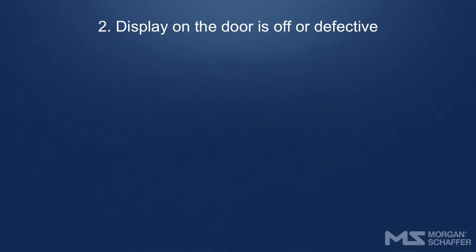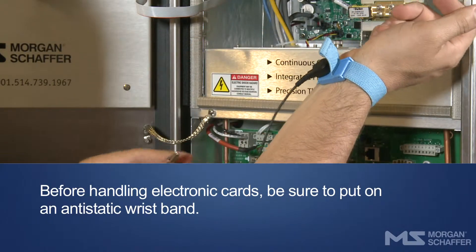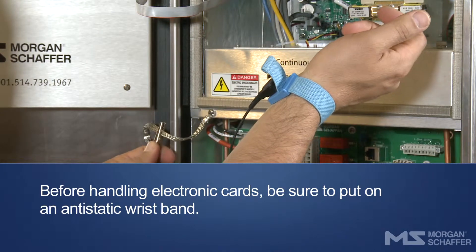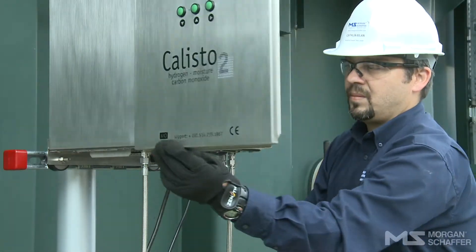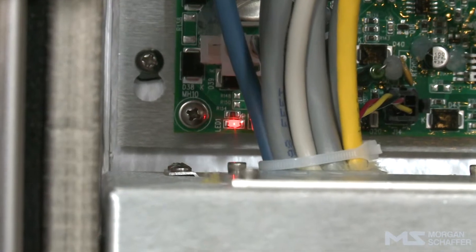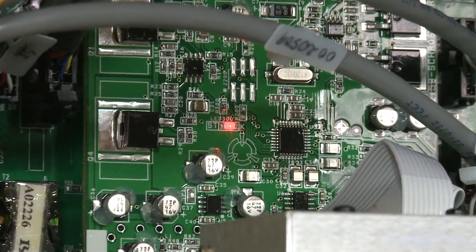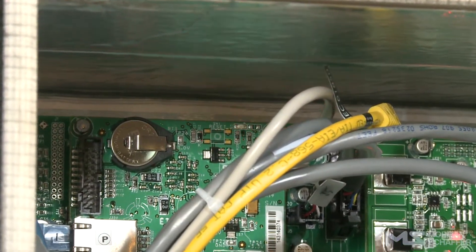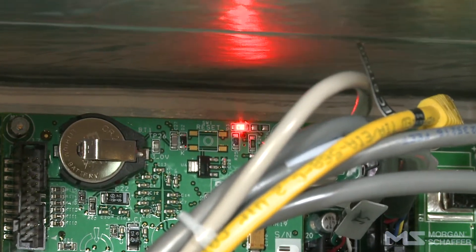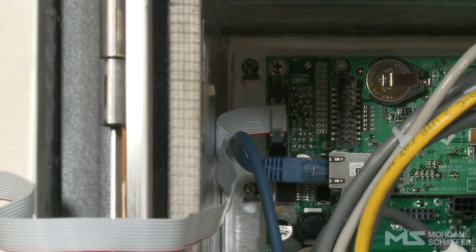Display on the door is off or defective. If the Calisto's display is off or incoherent, there is a problem related to the display or the power source. Before opening the Calisto, be sure to put on an anti-static wristband. Open the Calisto's door. Check whether the LEDs are working normally: the power LED is on, the cell's I/O card LED is on, and the central unit's LED is flashing. If this is the case, check that the flat cable connecting the display to the main I/O is properly connected at both ends.